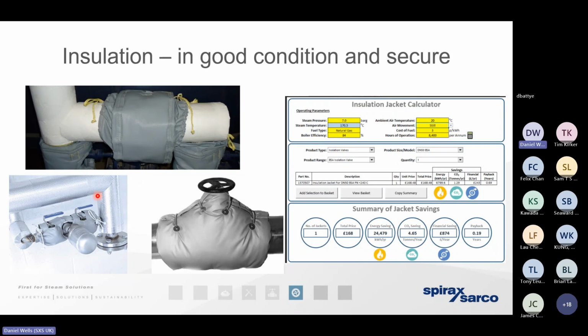We might need to allow a little extra capacity in the trap. So a lot of steam using sites would have had an infrastructure that was designed and engineered 40, 50 years ago, maybe. And at that time, water was plentiful. Cost of energy, the cost of gas was low. No one had heard about or cared about carbon emissions. So we lived with a certain degree of inefficiency for the simple reason that the payback in the insulation wasn't that great.